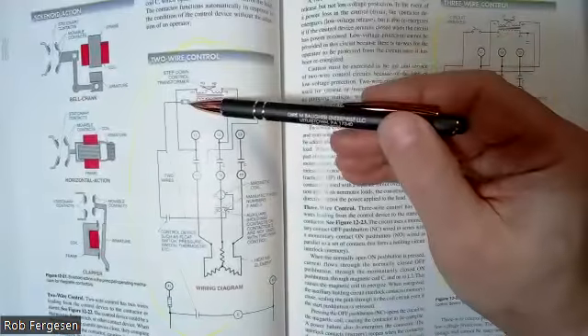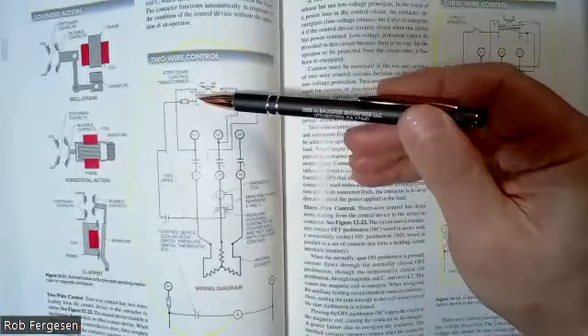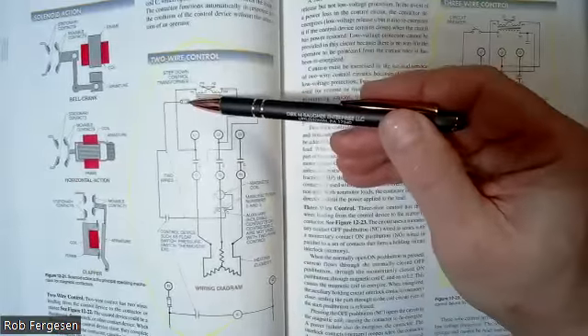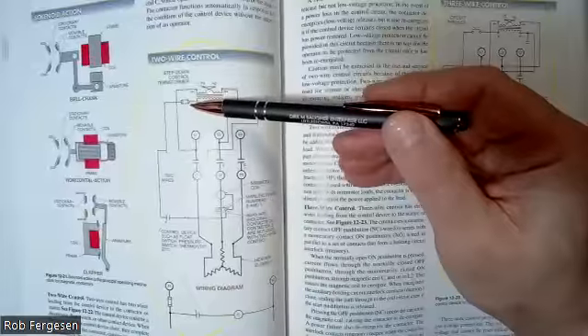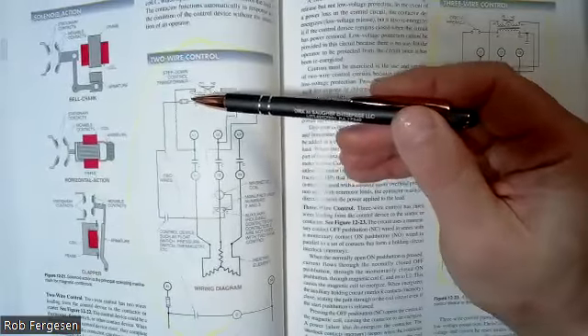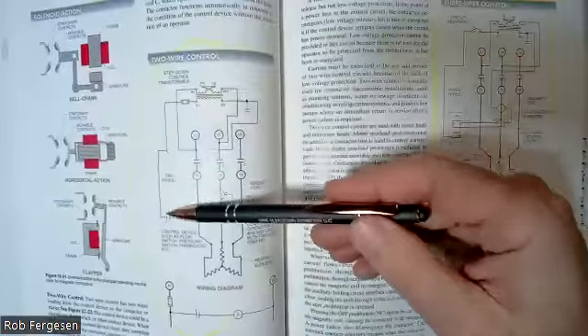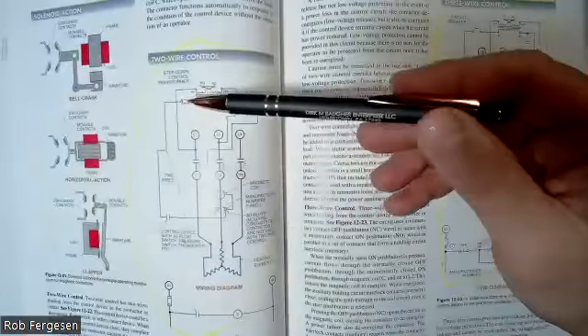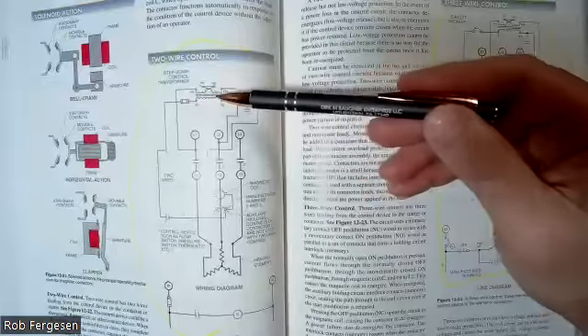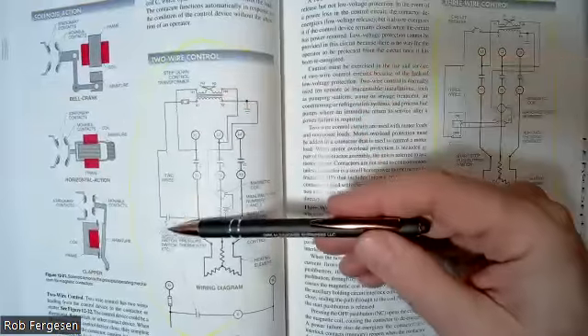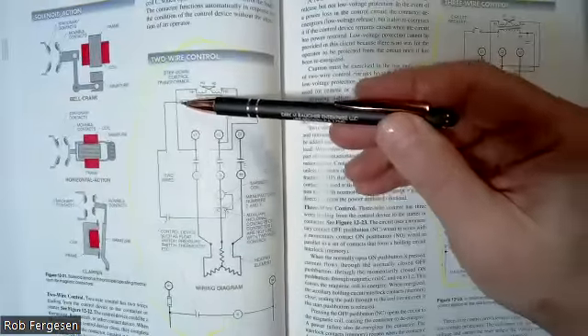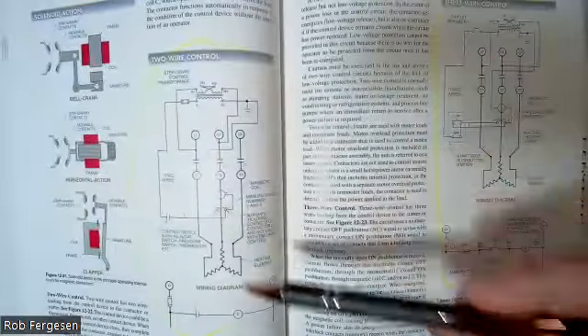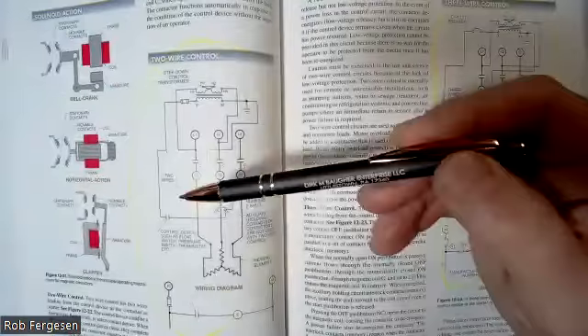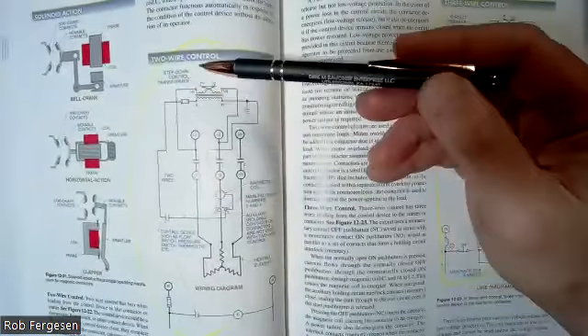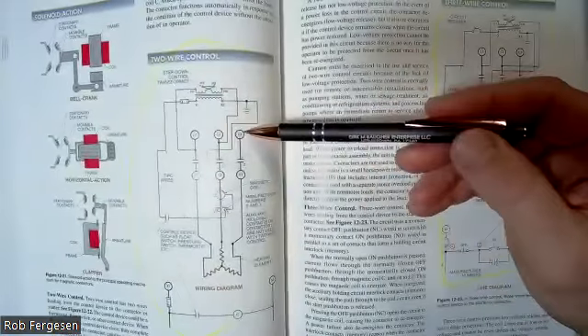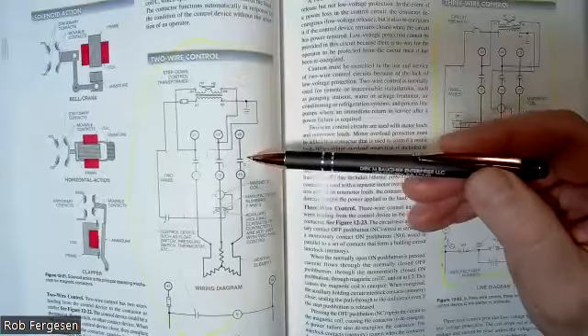Notice that I've got a little fuse symbol that I always put on my control transformer. That small fuse right there, usually 1, 2, or 5 amps, makes it so that if I short something out down here, then I will blow that fuse before I blow the transformer or melt one of the wires. So that fuse protects all of my control power. Then my legs are hooked to my contactor.